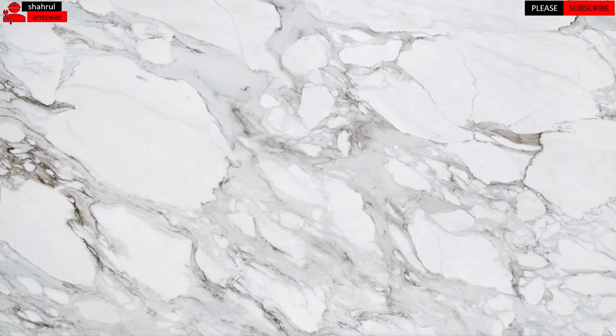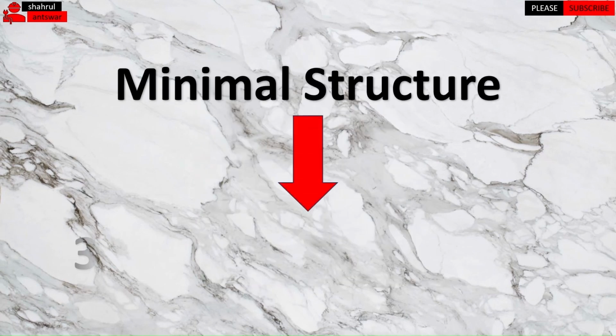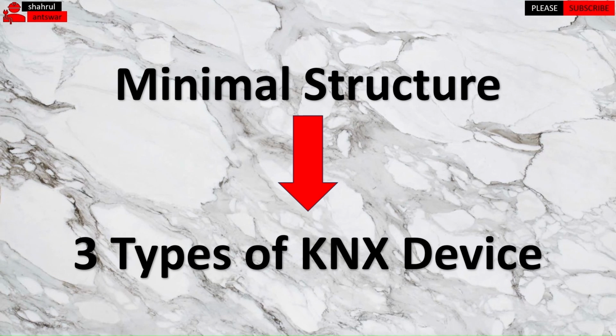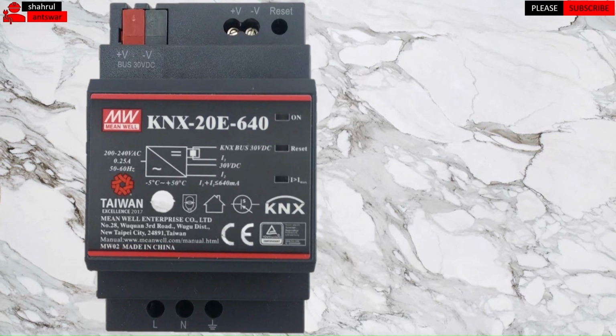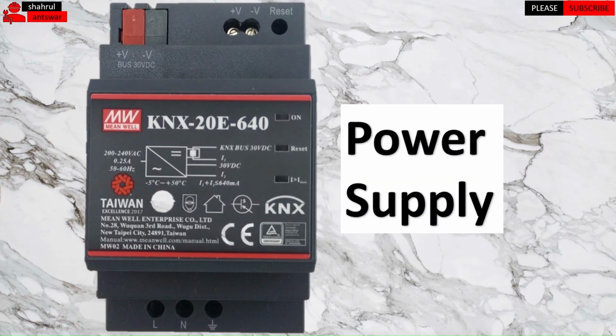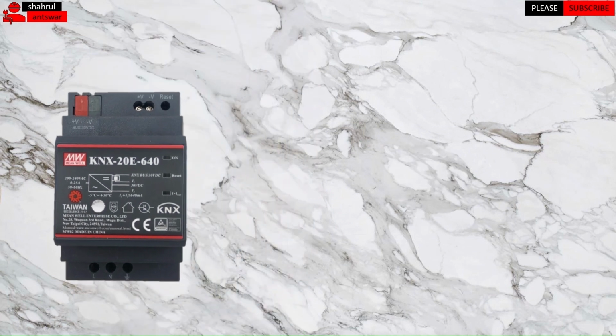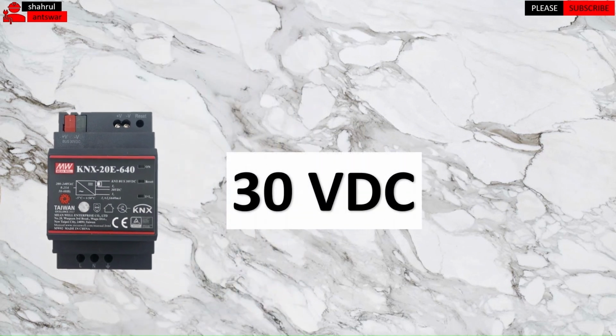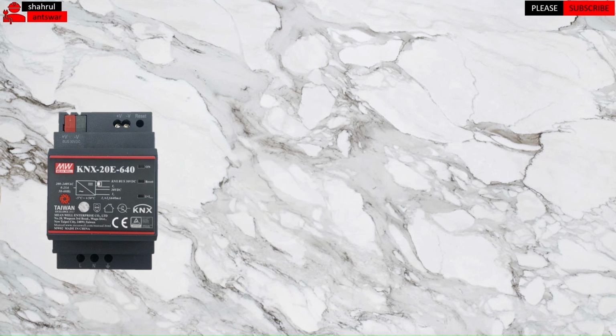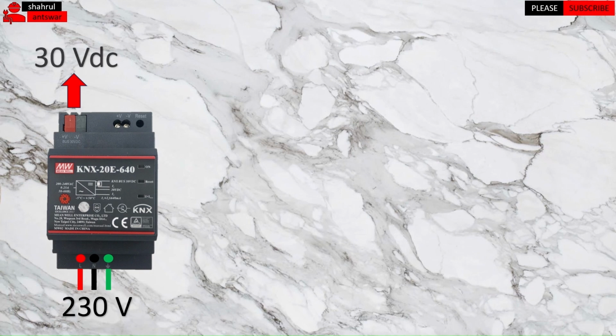For this video we will be introduced to the basic types of devices needed to complete a KNX system. The first device needed is a KNX power supply. The power supply functions to supply 30-volt DC voltage to the bus line. 230-volt voltage is connected to the power supply to turn it on. Next, this power supply will provide output voltage of 30 volts DC.